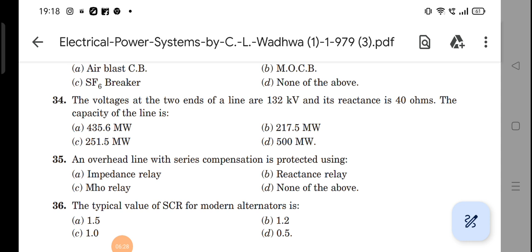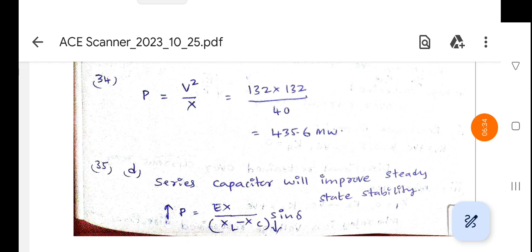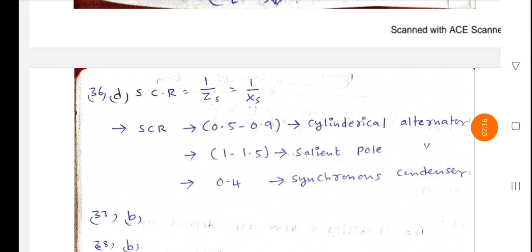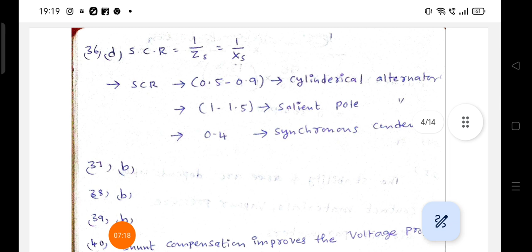Next: the typical value of SCR for modern alternators. SCR is short circuit ratio, given by 1 divided by ZS (synchronous reactance), or approximately 1 divided by XS. SCR ranges from 0.5 to 0.9 for cylindrical rotor or turbo alternators, from 1 to 1.5 for salient pole alternators, and is about 0.4 for synchronous condensers. From the given options, option D is 0.5, which lies between 0.5 and 0.9, so the 36th answer is D.